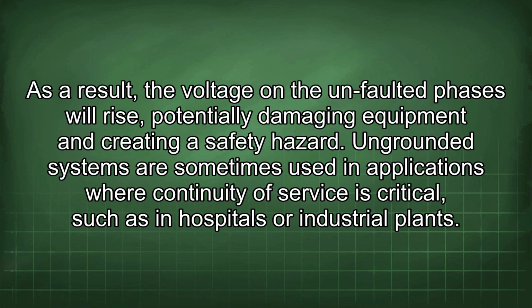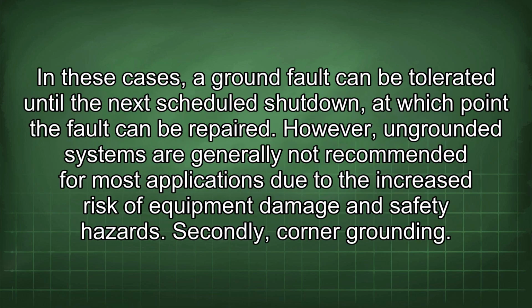Ungrounded systems are sometimes used in applications where continuity of service is critical, such as in hospitals or industrial plants. In these cases, the ground fault can be tolerated until the next scheduled shutdown, at which point the fault can be repaired. However, ungrounded systems are generally not recommended for most applications due to the increased risk of equipment damage and safety hazards. Secondly, corner grounding.